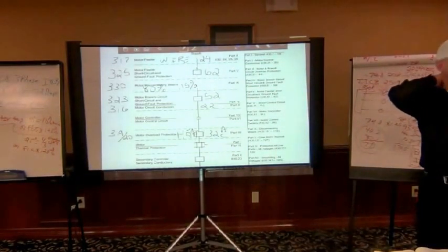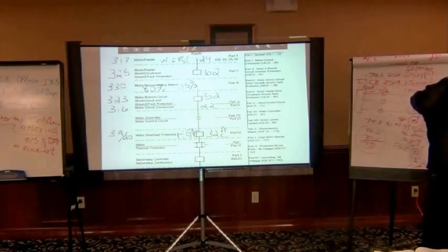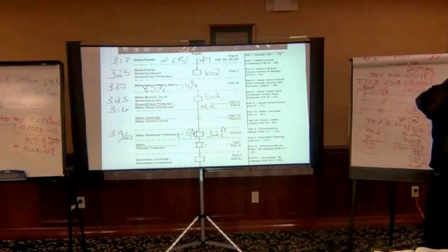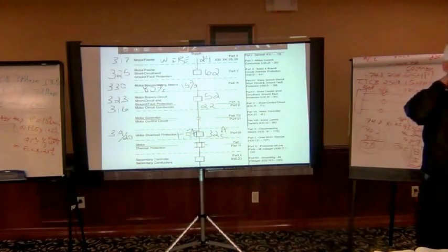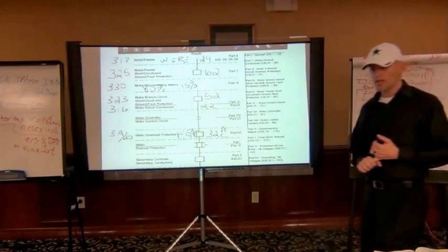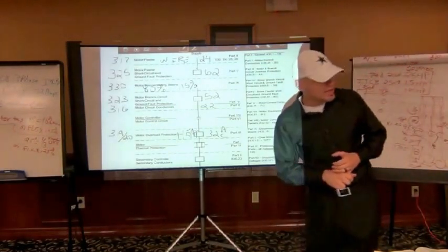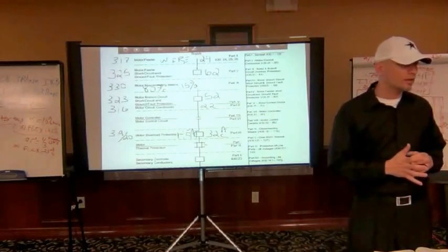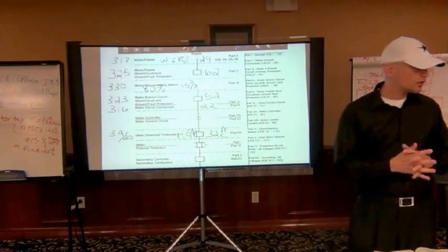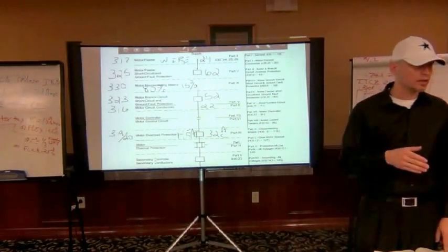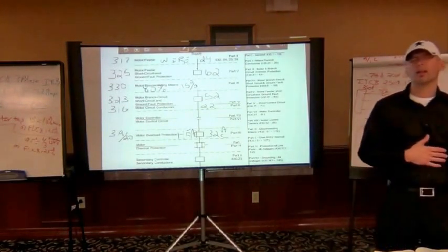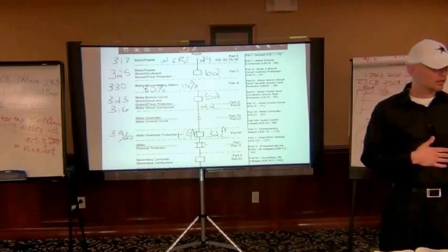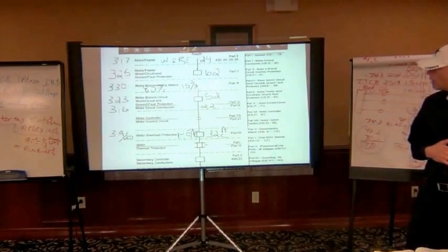Okay? Masters, you have one more table, 251B. If you guys will look at that real fast, you have one question out there that has to do with a fire pump motor. For fire pump motors, the overcurrent protection is going to be at the highest value you can set it at. That's based on the LRC because you want it to run indefinitely. What page is that? It'd be 339, I think. Yeah.